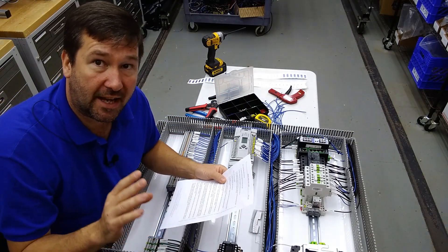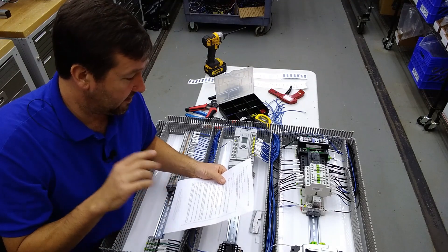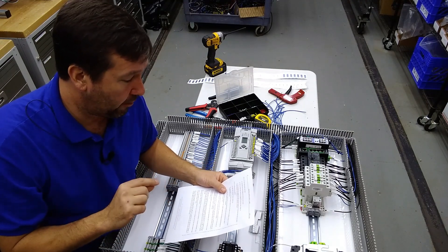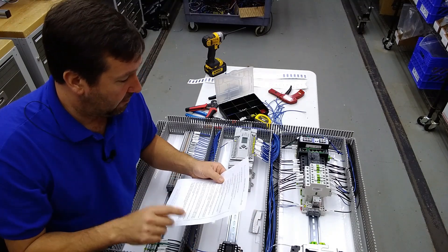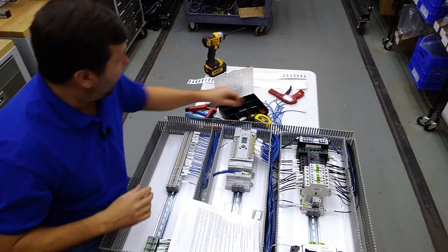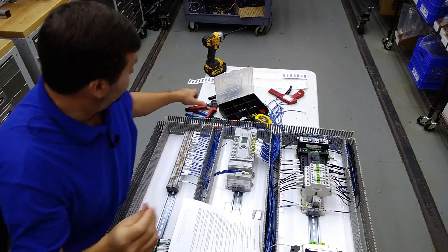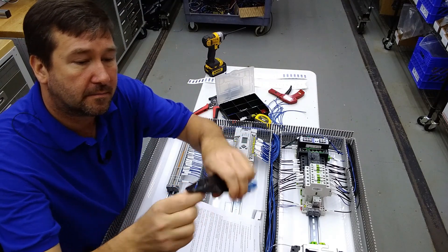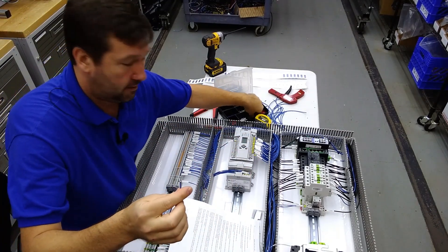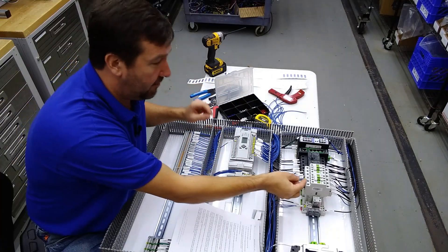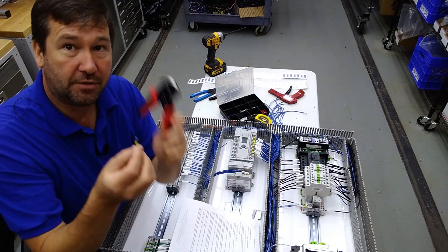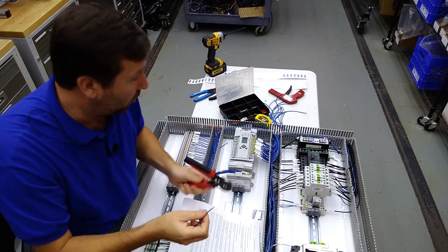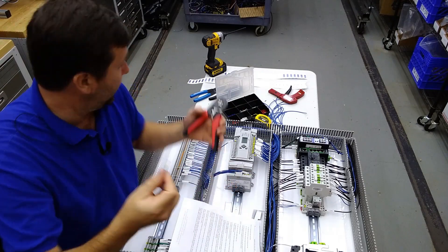The big one that UL really is a stickler on, at least my inspector is: it's crimped with the appropriate tool as recommended by the ferrule manufacturer before terminating in the terminal of a component. So what that is saying is don't take and strip your wire, stick your ferrule on, and then shove it into a terminal and tighten it down to crimp it. You have to use the proper tool before it is put into the connection. That right there is it.